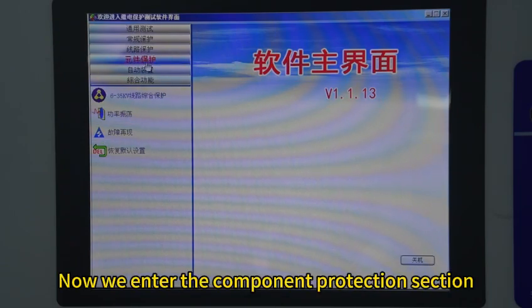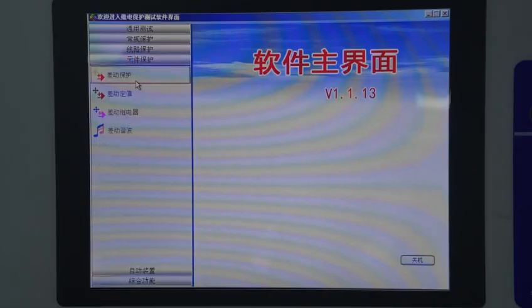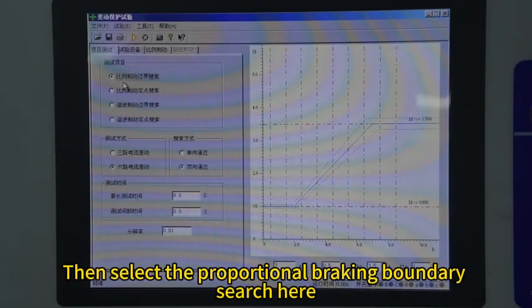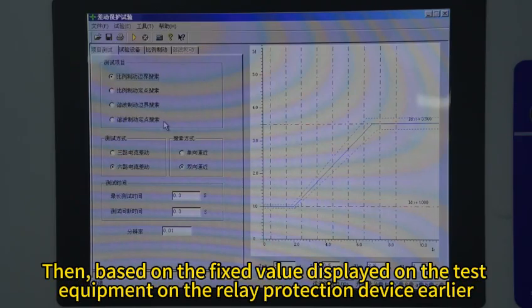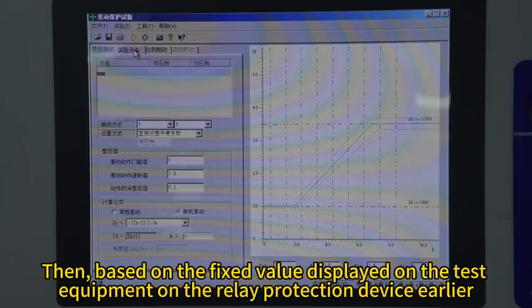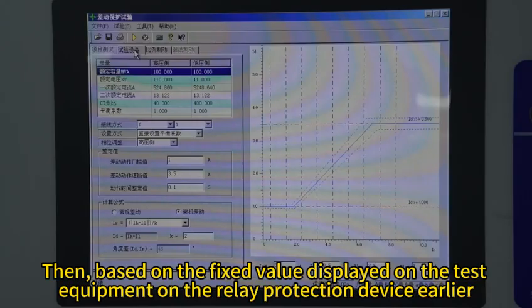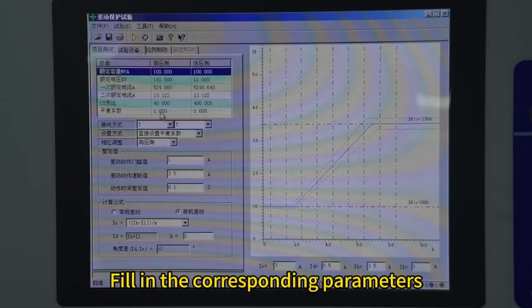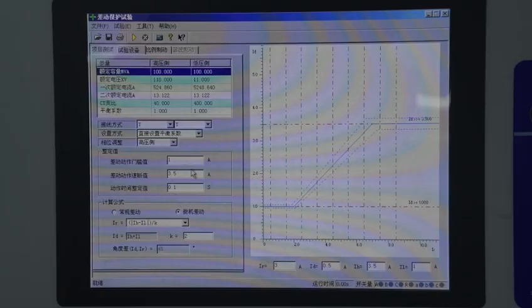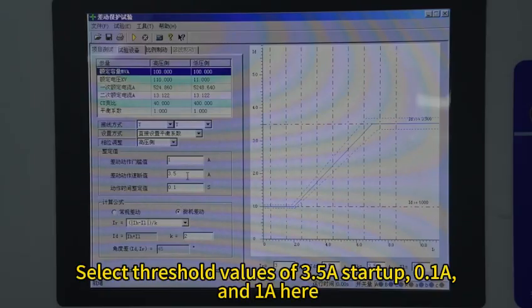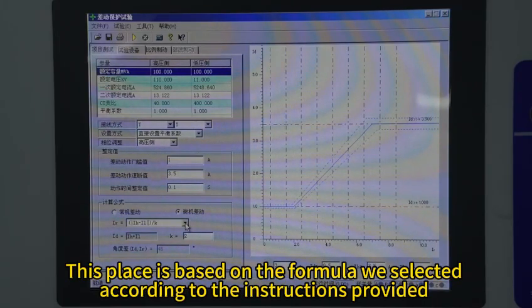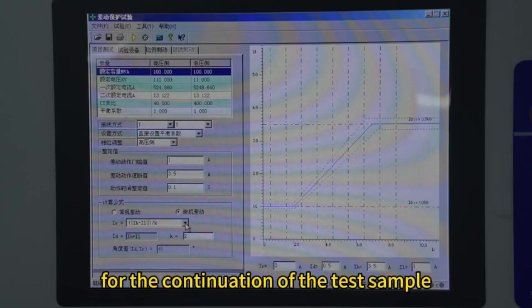Now we enter the component protection section. Select differential protection. Then select the proportional braking boundary search here. Then, based on the fixed value displayed earlier on the relay protection device, fill in the corresponding parameters. Select threshold values of 3.5 amperes startup, 0.1 ampere, and 1 ampere here. This place is based on the formula we selected according to the instructions provided for the continuation of the test sample.